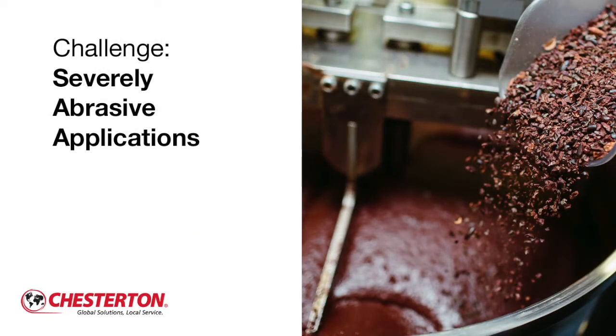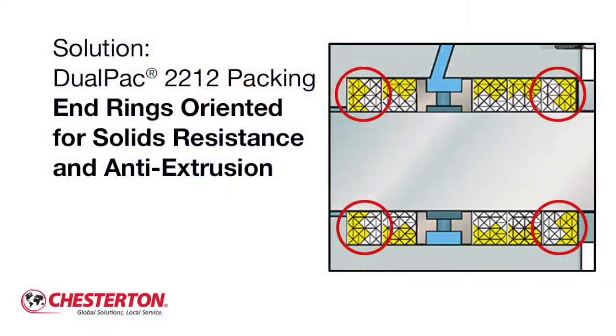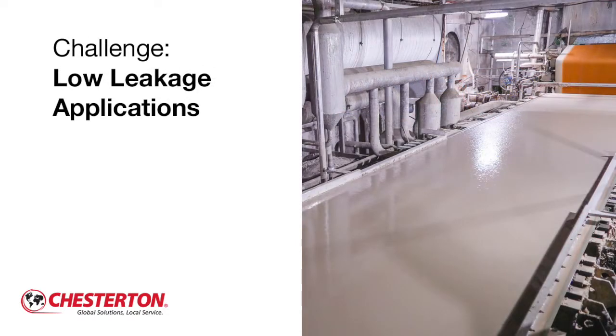For applications with abrasive media, such as in chocolate processing, an end-ring configuration can be used. Orient the two outer end rings with the yellow aramid facing outward for maximum abrasion resistance and to resist extrusion for longer packing life. Install the three inner sealing rings with the white side toward the shaft to protect the shaft from wear.